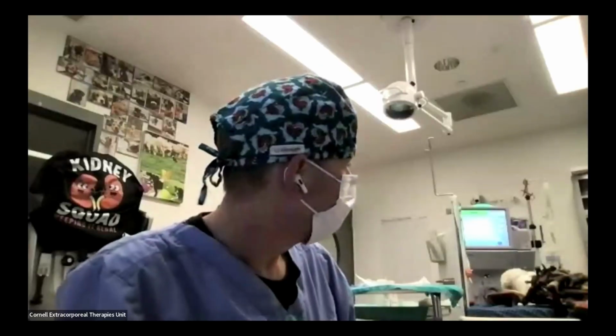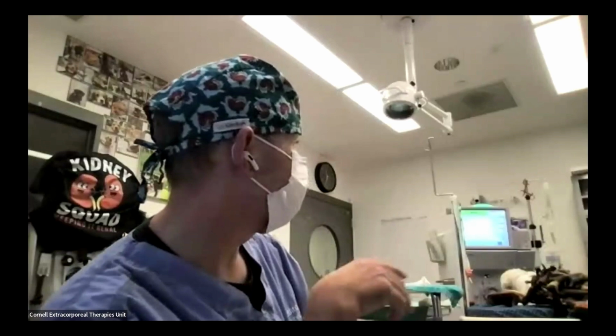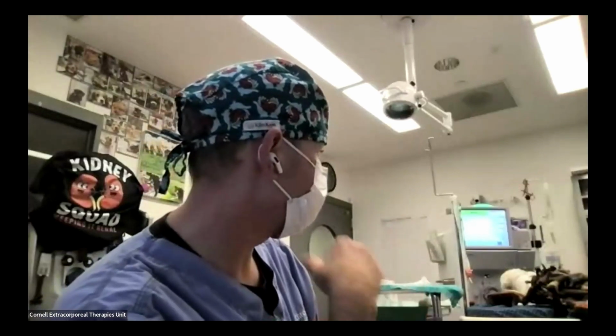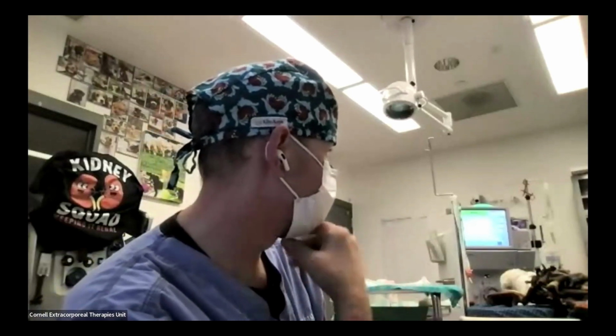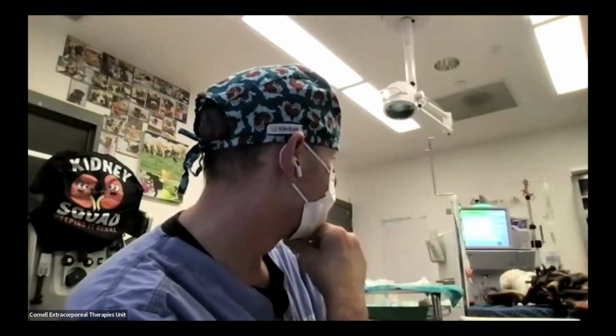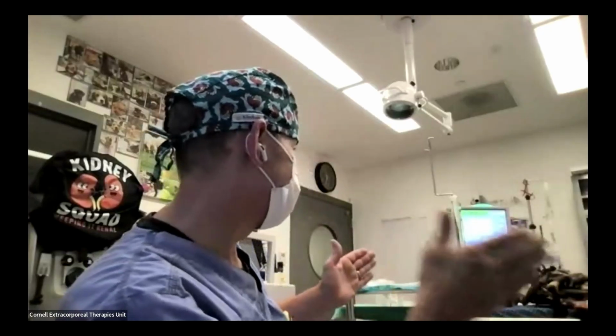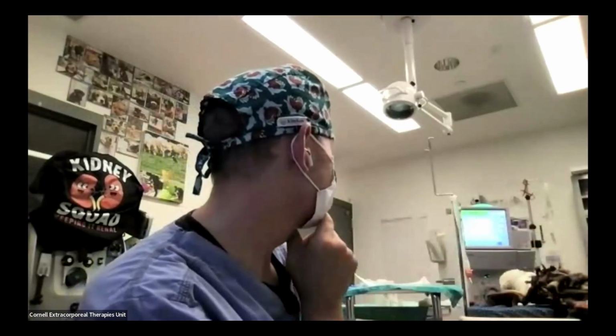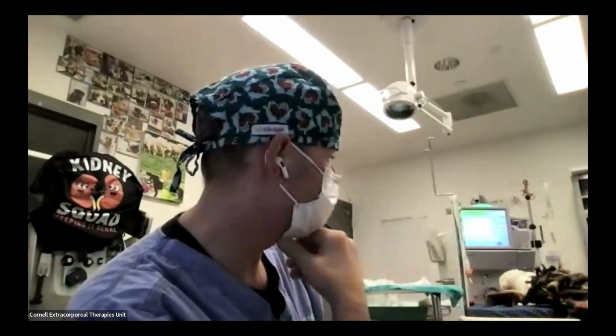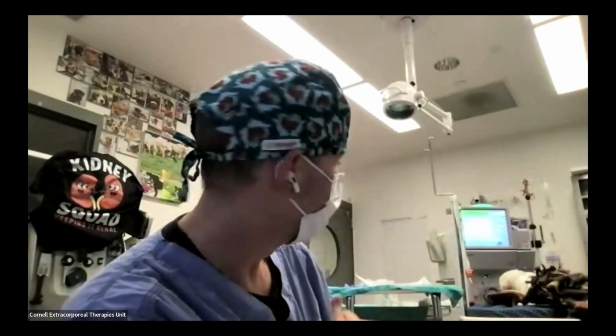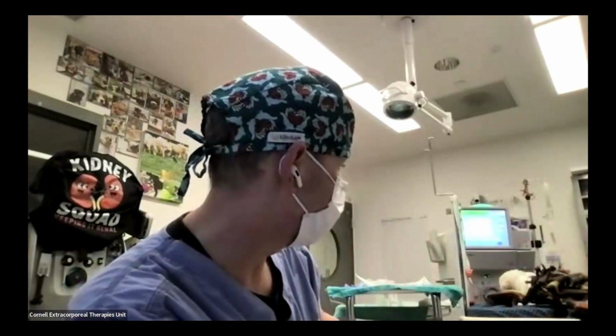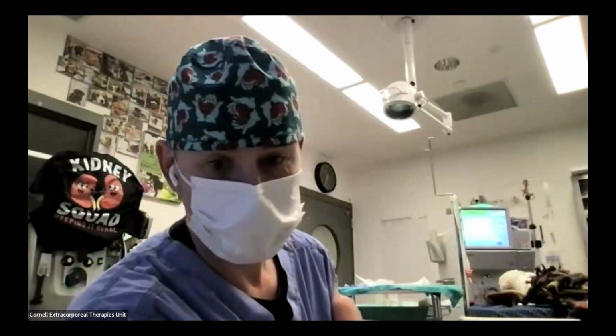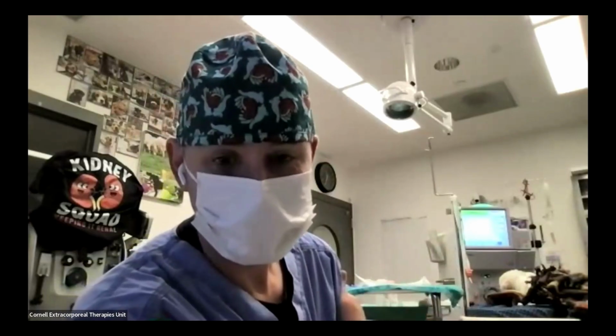Right. Just now, maybe my back was occluding it, but maybe like 20 minutes ago when I leaned over, we had maybe half that access line filled with air. It just kept pulling it in, and obviously the catheter was sucked up against the cava inside of Molly. But the pump didn't stop, and it pulled all that air in, and then it filled the air detector chamber, and then we got air detector alarms.